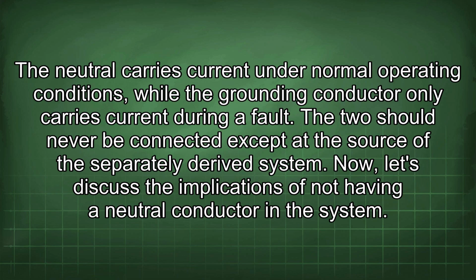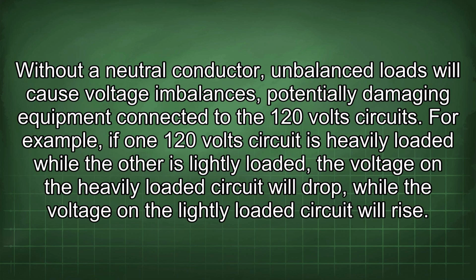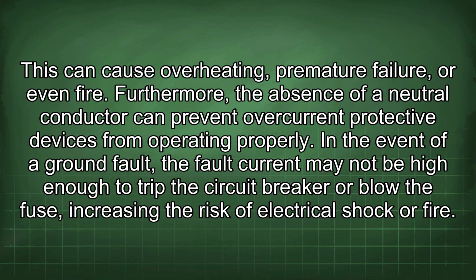Now let's discuss the implications of not having a neutral conductor in the system. Without a neutral conductor, unbalanced loads will cause voltage imbalances, potentially damaging equipment connected to the 120-volt circuits. For example, if one 120-volt circuit is heavily loaded while the other is lightly loaded, the voltage in the heavily loaded circuit will drop, while the voltage in the lightly loaded circuit will rise. This can cause overheating, premature failure, or even fire.